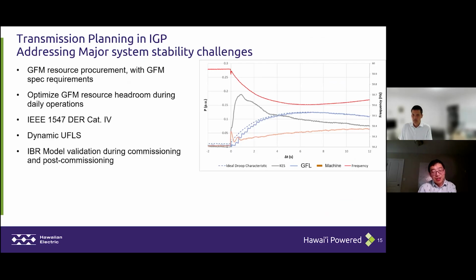We're addressing all those stability challenges right now and trying to look into many different ways at the same time. So we mentioned before the grid forming resource procurement, which is a really important one. Starting from stage 2 RFP, we require all the IBR facilities to first pair with BESS, and then the BESS needs to be grid forming BESS. We do not take grid following controlled BESS. And we optimize the grid forming resource headroom during daily operation. So we try to have enough headroom from grid forming resources to respond to those large contingencies and address the DER momentary cessation issue.